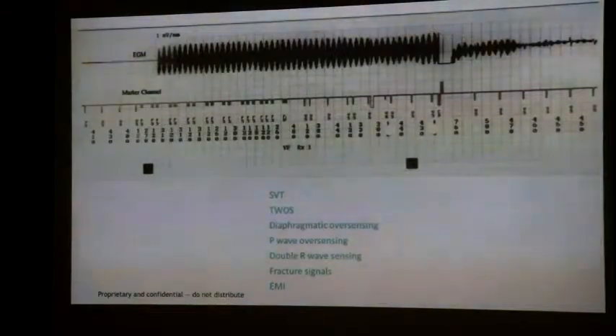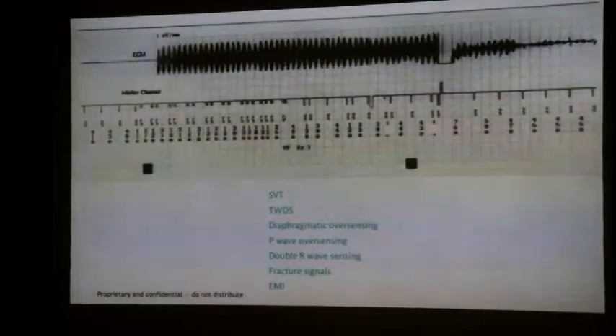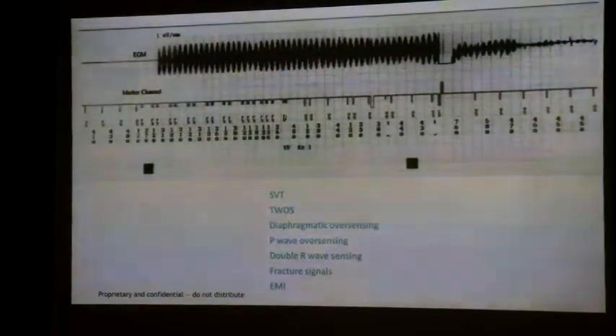So, what's this one then? This noise here. This is an RV lead. So this is a patient really well connected to mains. You can see the mains going. This is the mains frequency. They're connected to the mains electricity, the power sockets. They're not doing this, but they're connected.